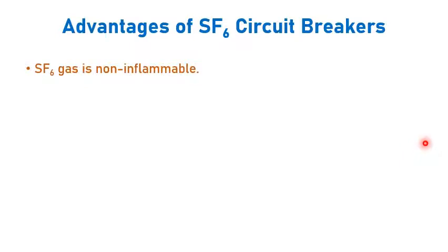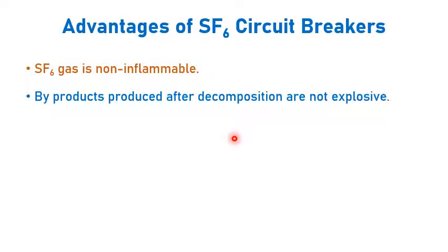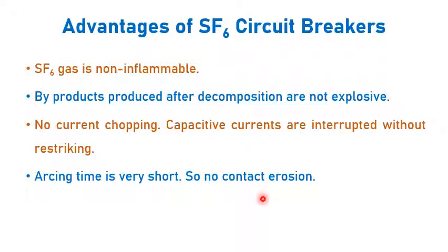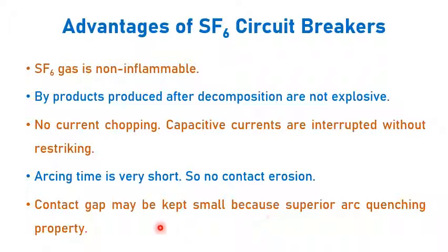Advantages of SF6 circuit breakers: SF6 gas is non-inflammable and the byproducts produced after decomposition are not explosive. No current chopping is possible and capacitive currents are interrupted without re-striking. The arcing time is very short because SF6 gas quenches the arc at a faster rate, keeping the contacts very safe. Also, you can keep the contact gap very small — even a small gap is enough to quench the arc.